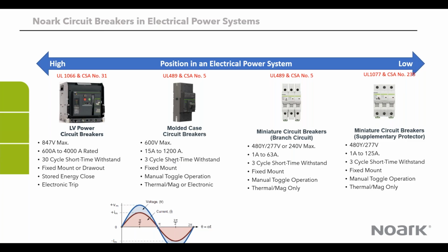If you have it in that kind of design, what it means is that while the downstream breakers are trying to react to a fault, your main breaker is also going to be reacting at the same time. And what it means is that you can have a downtime here, because if the main breaker is off and you have other feeders or other LD feeders in the system, it's going to lead to a loss of service for the other LD feeders. So that's what the short time withstand is really all about, and how we use it in electrical system design.